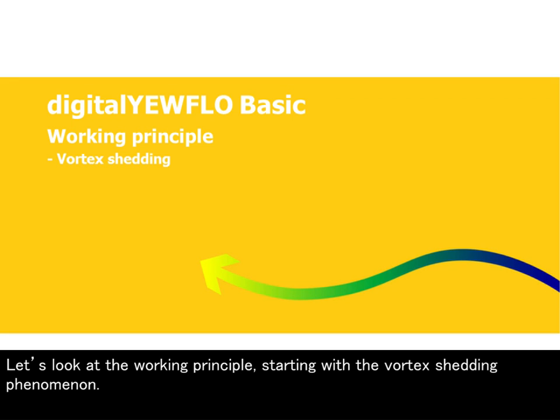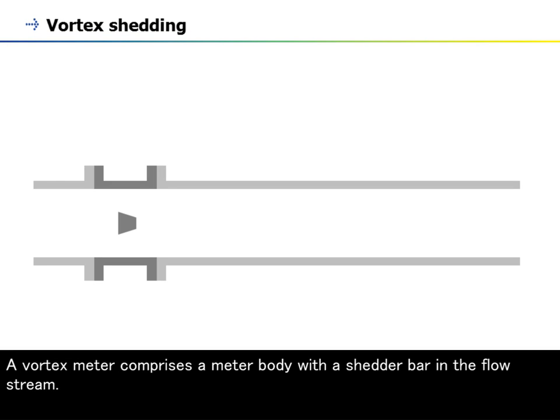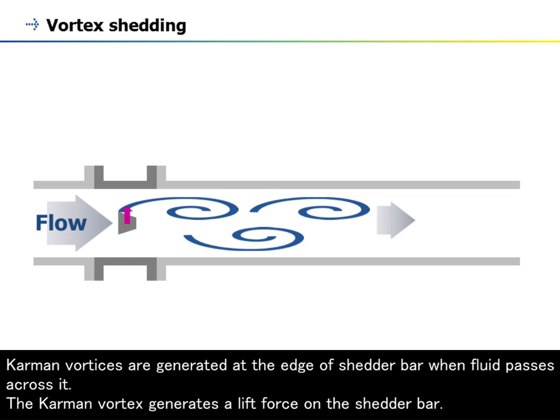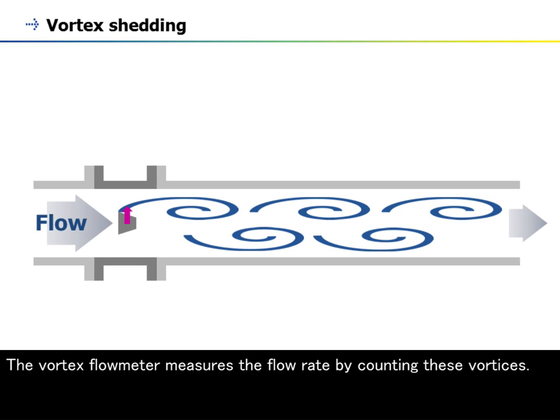Let's look at the working principle, starting with the vortex shedding phenomenon. A vortex meter comprises a meter body with a shedder bar in the flow stream. Karman vortices are generated at the edge of shedder bar when fluid passes across it. The Karman vortex generates a lift force on the shedder bar. The vortex flow meter measures the flow rate by counting these vortices.